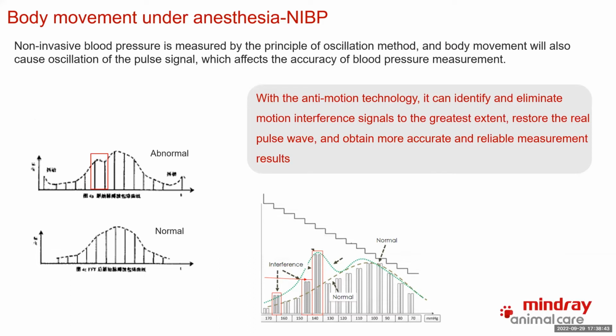principle of the oscillation method. So that means the body movement will also cause oscillation of the pulse signals. So it's the same when you measure the NIBP, there's oscillation caused by the blood flow and there's oscillation caused by the body movement. So for other brands, they cannot tell which part is the real oscillation to measure the NIBP. But for us, we have this anti-motion technology. It can identify and eliminate the motion interference signals, and also restore the real pulse wave and obtain more accurate and reliable measurement results.